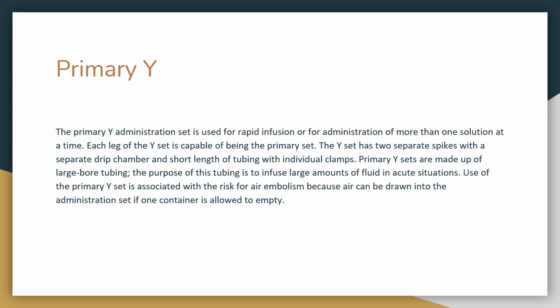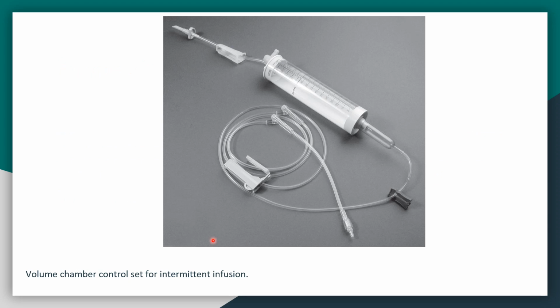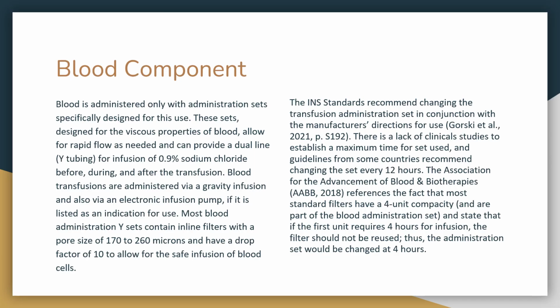Okay. Use of the primary Y set is associated with the risk for air embolism because, again, the air can be drawn up quickly. This is a volume chamber. So this is what holds the volume. Very rarely used nowadays. You see these in neonatal units and everything where this is the volume that we're infusing, so it has to be very precise, but not used often.